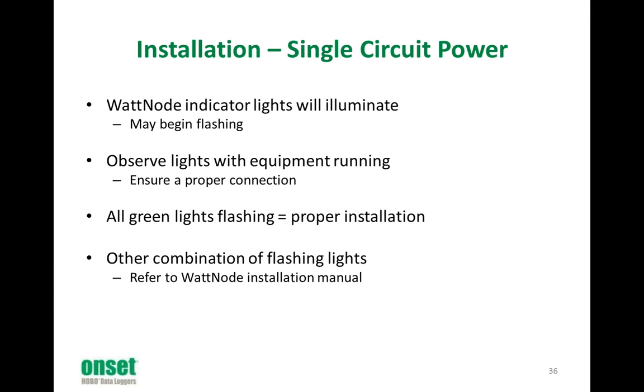And one thing to emphasize is that with the equipment not running, you might have slow green light flashing, slow yellow, slow red. That might be normal. So it's important: the only time to believe those lights is with the equipment running and with the WattNode seeing a true load.